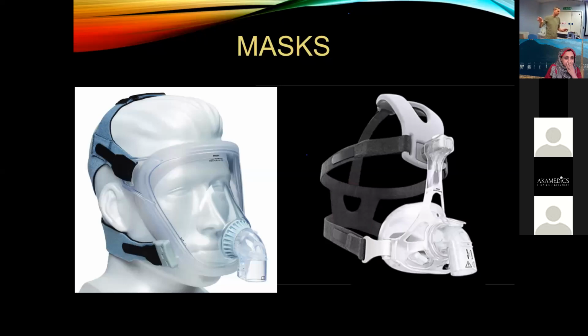Hopefully you guys are familiar with the settings and how they work. I would just like you to show the circuit and everything. What is the filter going through? In terms of leak, I'm not sure about the ResMed because I did look, and it said that it has leak compensation, but it didn't say to what amount. The Respironics devices have a leak compensation up to 60 litres per minute. So if there's an air leak of up to 60 litres a minute, for those of you using the Respironics machines, the machine will compensate for that and just deliver extra pressure to compensate for that leak.